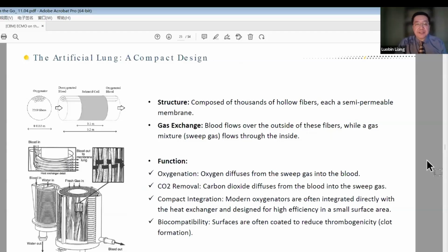The same as oxygenator. We need a better material. We need a better oxygen membrane for a better gas exchanger. So to get a better oxygenation and the CO2 removal. So the oxygenators are often integrated directly with a heat exchanger. So we can build it together. We can design a high efficiency in a small unit.